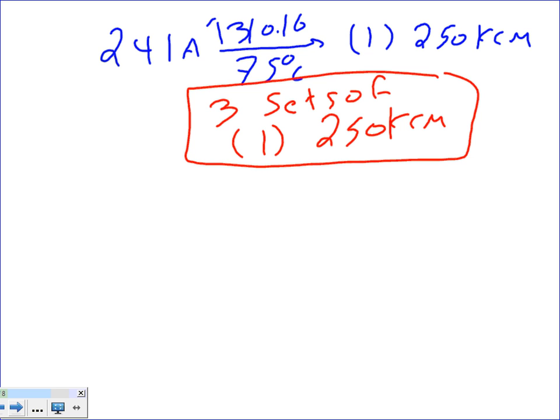See how the price becomes a major factor here, where you don't need to. I can go make them 350 and it's fine, it meets the code. But imagine how much you're going to pay for 3 sets of 350 instead of 250. That could make or break your bid, a big chunk. It depends on how long you're running this. If you go that size jump, I guarantee you're adding at least 25% extra on that particular run, all things considered.